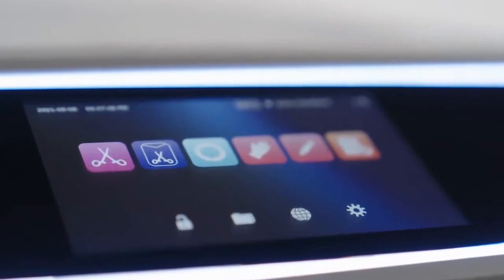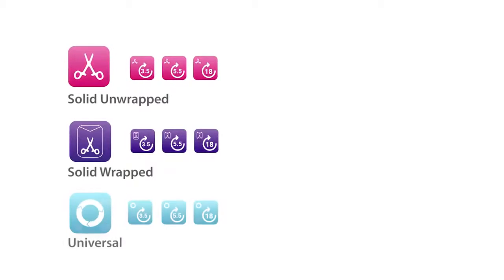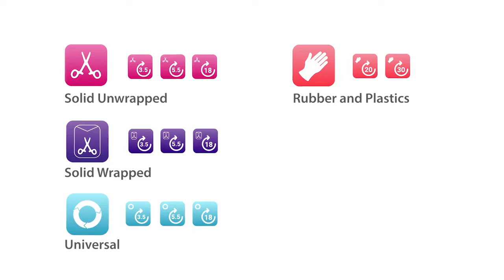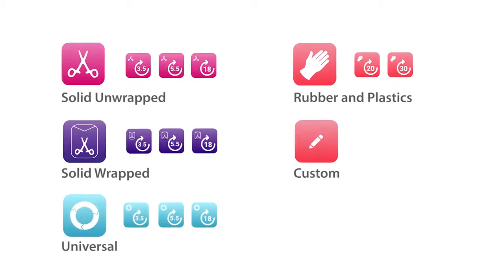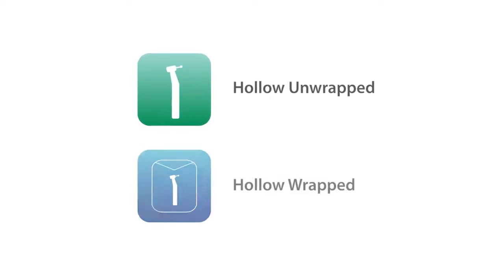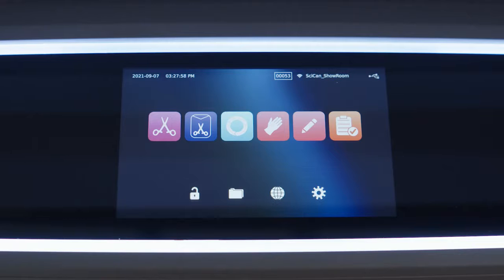The STATIM B has several sterilization programs, each with a selection of holding times and each optimized for fast and effective drying. Cycles include solid unwrapped, solid wrapped, a universal cycle, and a rubber and plastic cycle. The unit also has 2 custom cycles. And units in some markets may also have hollow unwrapped and hollow wrapped cycles. The STATIM B also offers test programs to periodically check the unit's effectiveness.